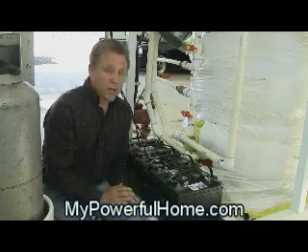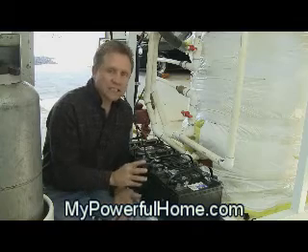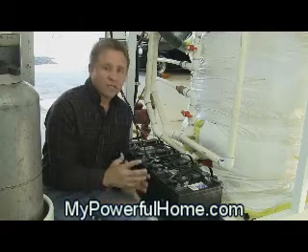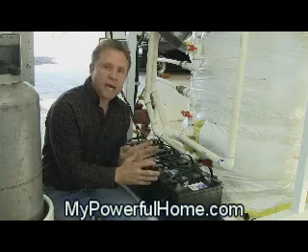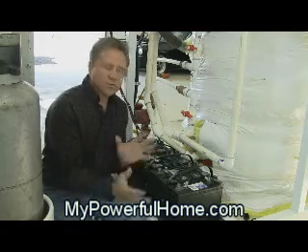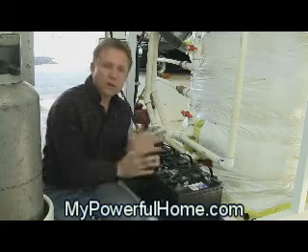Now, an important point: don't just grab a bunch of batteries and throw them together thinking they're going to work properly. If batteries are dissimilar — different types, different amp hour capacities — it's really going to wreak havoc and your batteries aren't going to last very long. The age of a battery matters too. You may have similar batteries, but if some are depleted or their cycle life is shortened because they've been used a long time, and then you throw a couple of new batteries in there, it's going to degrade the whole battery bank. Try to replace all your batteries when their life cycle is over. It's very important, or it's going to affect your new batteries. You want to get all the cycles you can out of your batteries.